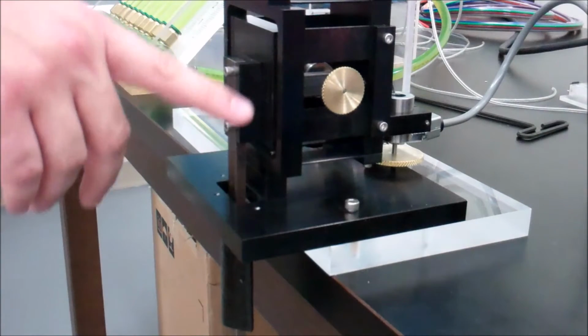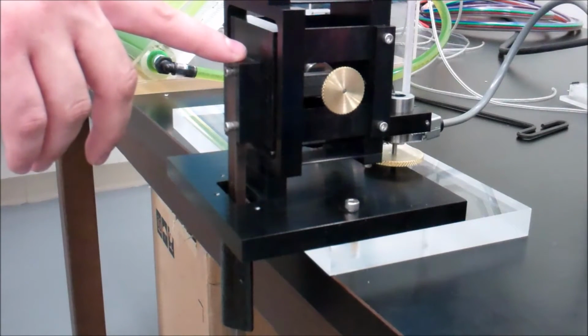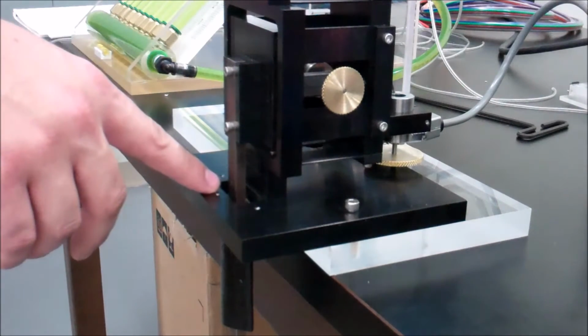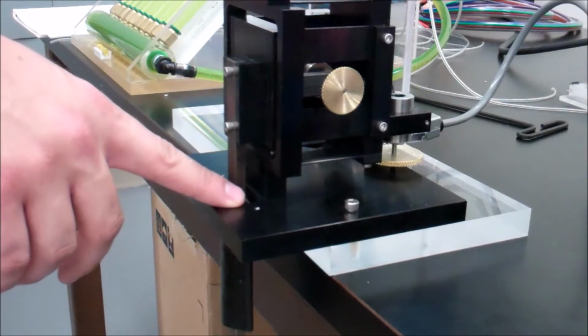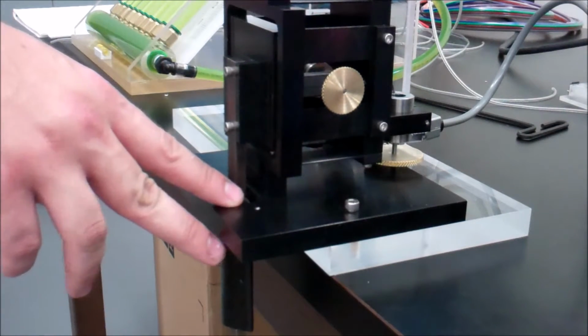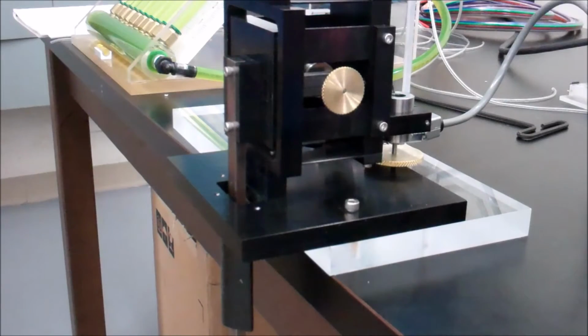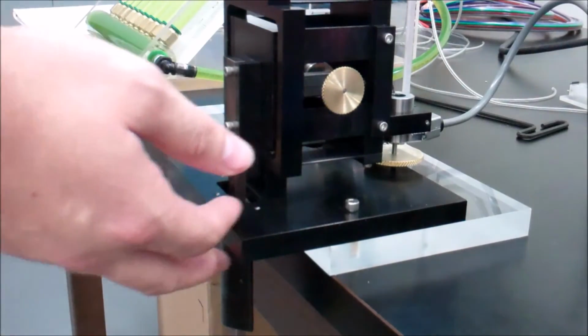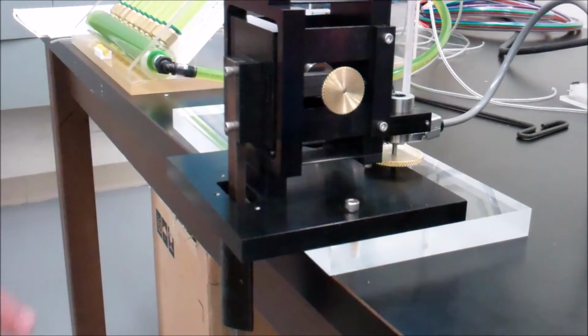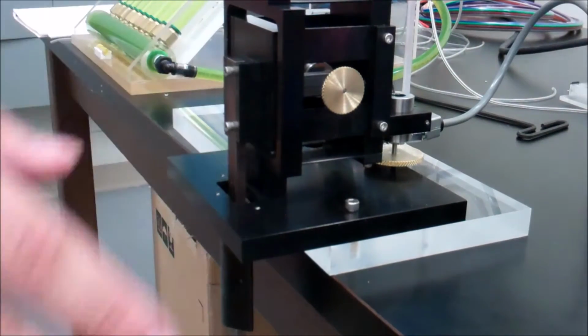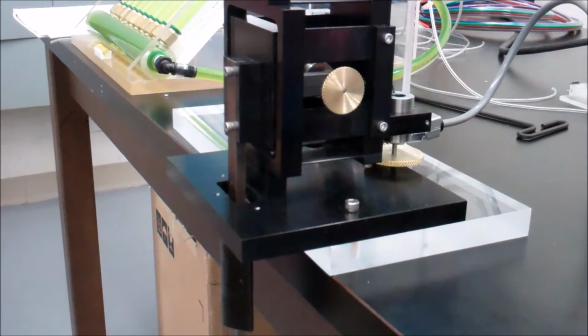Now there is a limitation on how much force this unit can display, and that limitation is 35 newtons, which is equivalent to 3.5 kilograms. So do not put more than 3 kilograms on this unit and you'll be fine. So calibrate between 0 and 3 kilograms when you apply weights to this. And now, once you're finished with the lift, we need to go on to the drag.